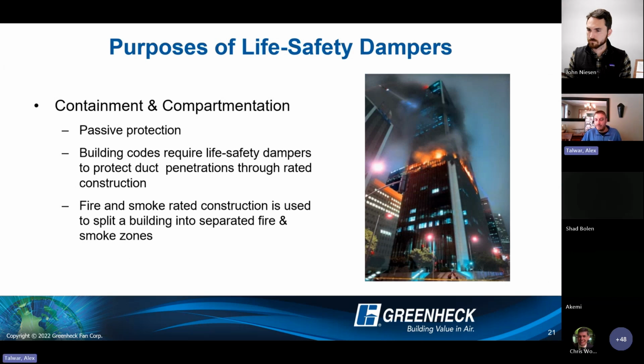All right, in terms of purposes of the products, I kind of touched on this already. The International Building Code requires that we put these products in there, but why do they require it? Ultimately, to prevent the spread of flame or smoke throughout a building, compartmentalize larger buildings into smaller zones, ultimately creating a longer amount of time for people to get to safety and for the building to maybe even stay intact and not collapse. So a lot of reasons why these products are required and why they have the title life safety dampers. They are saving lives.